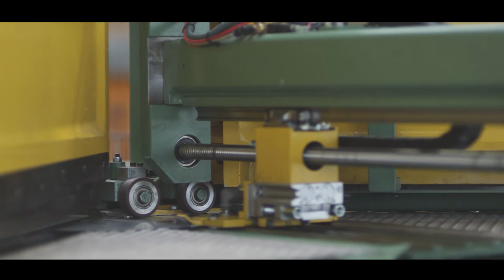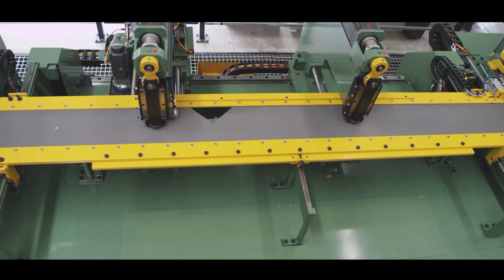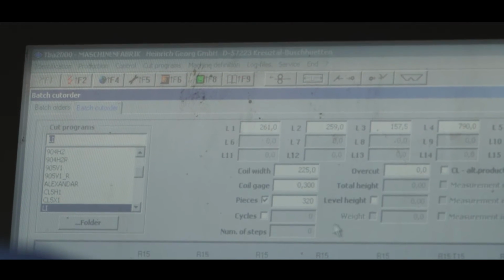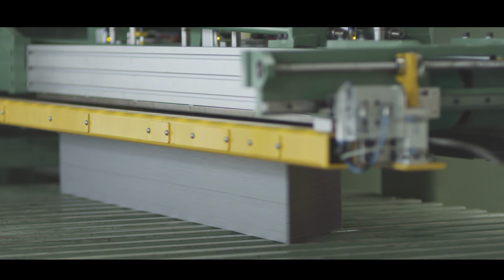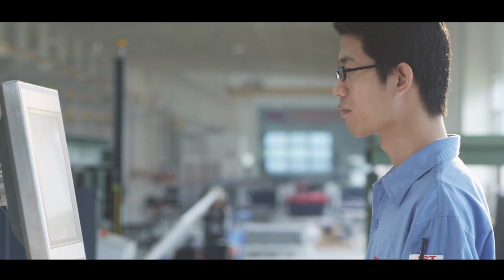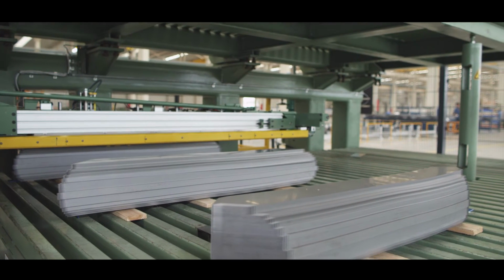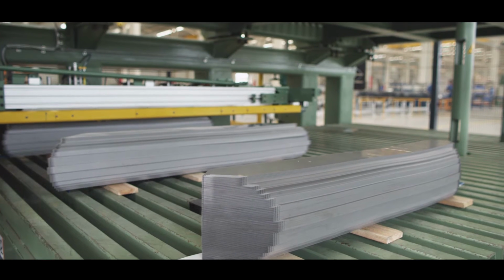and under computer control. The core cutting machine selects the correct core width and then cuts a series of laminates, each stepped in length, before automatically selecting the next strip width to achieve the desired cylindrical cross-sectional geometry of the core leg. Each laminate is automatically stacked on a stacking table during this process. The end result is a core leg held within the strict tolerances to achieve the desired core geometry.